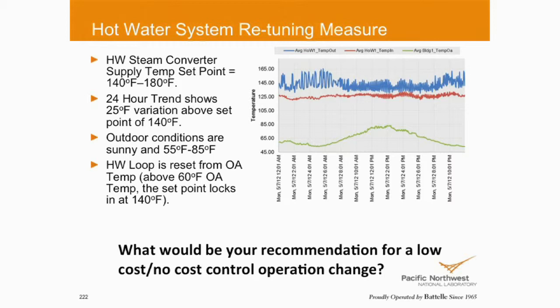And again, outdoor conditions, sunny, 55 to 85. It's from the same location we talked about earlier this morning. So this is California. And the hot water loop resets based on anything above 60 degrees. So once it gets above 60 degrees, it's locked at 140 degrees.